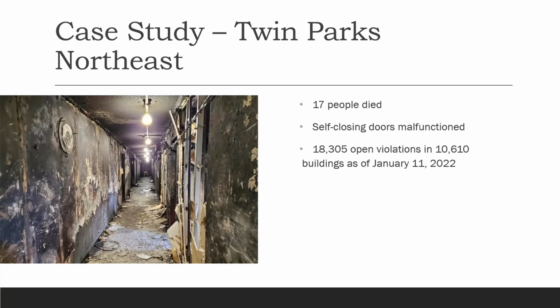The fire commissioner singled out malfunctioning self-closing doors as a key reason smoke from the flames quickly engulfed much of the 19-story tower. What's even worse is that inspectors from the city's Department of Housing Preservation and Development cited the tower 6 times between 2013 and 2019 for failing to keep all of the building's self-closing doors in working order. 4 years prior to this devastation, the Prospect Avenue fires took the lives of 13 people. What happened was an open door fanned the flames in a blaze that consumed that building.